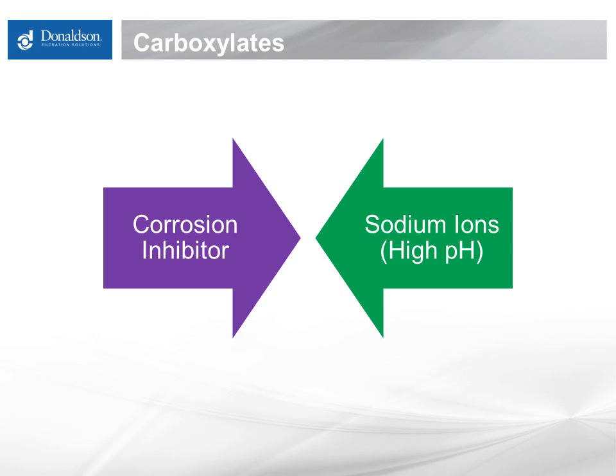The metal carboxylate we are most often seeing is created by a reaction of common corrosion inhibitor chemistry found in diesel fuel and sodium ions in a high pH condition — that is a caustic or basic situation, not an acid condition. This reaction can occur at the time of fuel manufacture, before transport, or possibly in tanks with high pH conditions in the tank bottom water. The reaction forms a huge amount of tiny particles that tend to stay suspended and float around in the fuel. They are so small — generally one to three microns — that they don't settle out into the tank bottoms and are not captured by traditional levels of filtration.